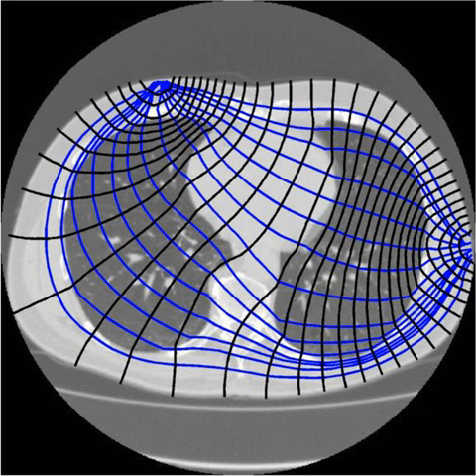In contrast to most other tomographic imaging techniques, EIT does not apply any kind of ionizing radiation. Currents typically applied in EIT are relatively small and certainly below the threshold at which they would cause significant nerve stimulation. The frequency of the alternating current is sufficiently high not to give rise to electrolytic effects in the body and the ohmic power dissipated is sufficiently small and diffused over the body to be easily handled by the body's thermoregulatory system. These properties qualify EIT to be continuously applied in humans, e.g. during mechanical ventilation in an intensive care unit.